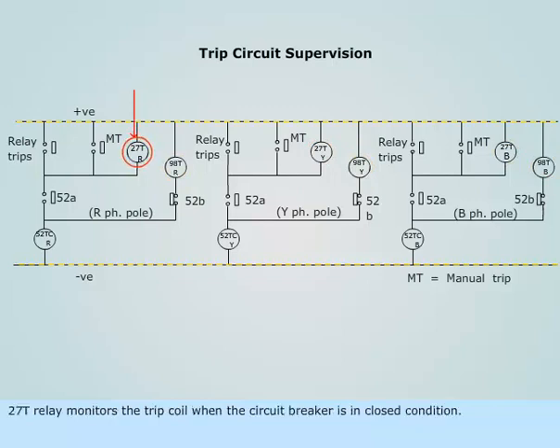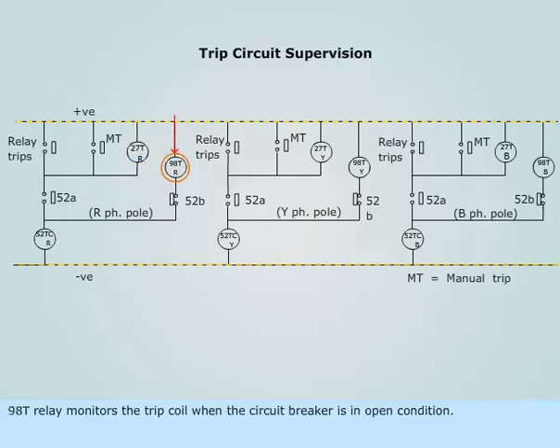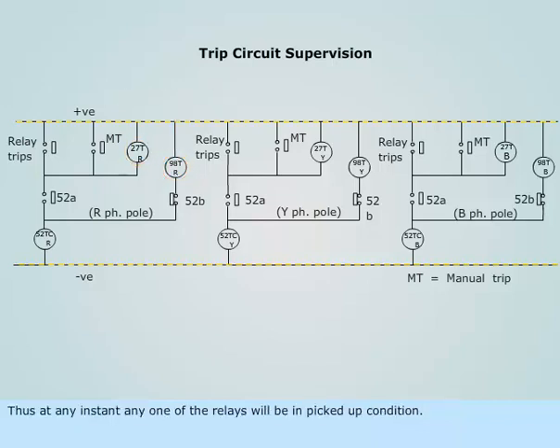27T relay monitors the trip coil when the circuit breaker is in closed condition. 98T relay monitors the trip coil when the circuit breaker is in open condition. Thus, at any instant, any one of the relays will be in picked-up condition.